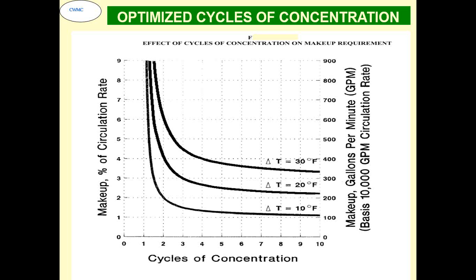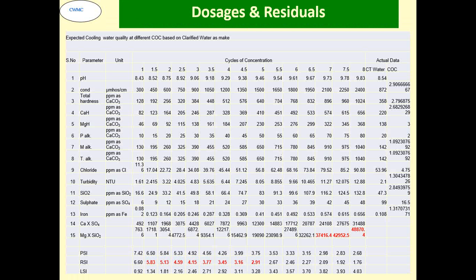But in some places you might be able to go even higher, because I know one of the stations where, as I said, 10 ppm hardness, 10 ppm alkalinity was there. That station, they are operating about 15 COC without any chemical treatment. But that is dependent again upon the station to station.